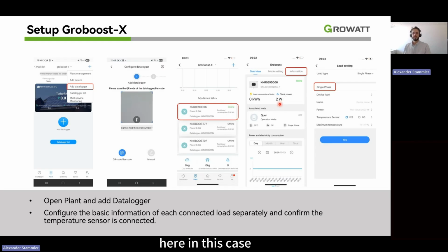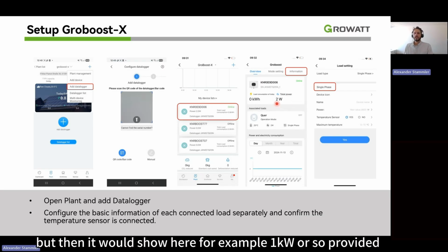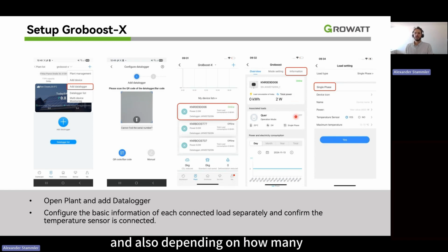In this case it was offline, but otherwise it would show here, for example, 1 kilowatt or so being provided. And also depending on how many loads you actually connect, whether only one phase or the three phases, you need to set up how many loads you connect to the Groboost-X. If you go to information, you can here see the load is single phase. You can change it to three phase, and then give it a name, for example, my immersion heater in the cellar.